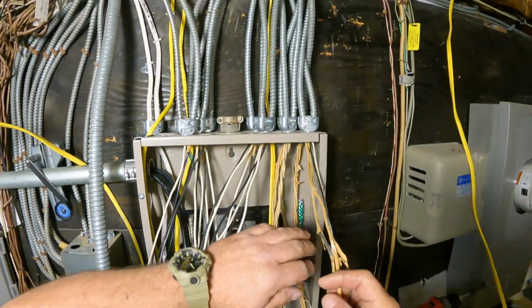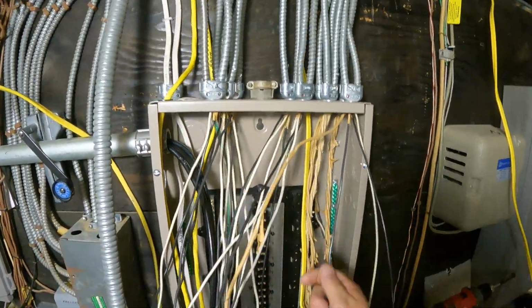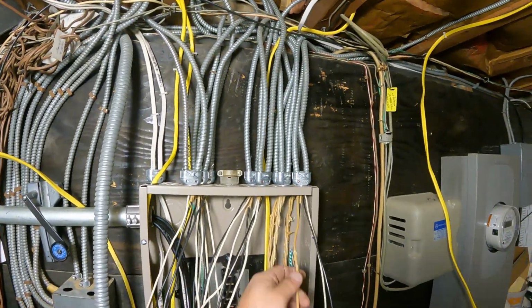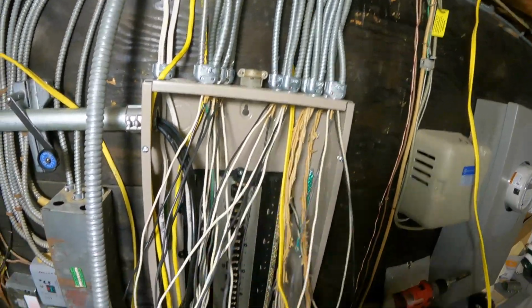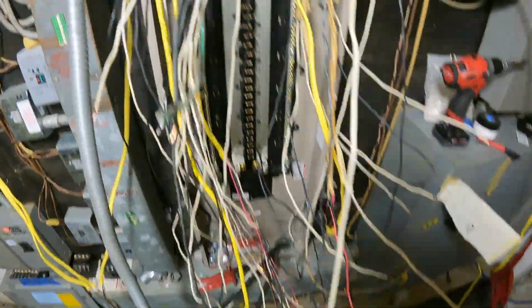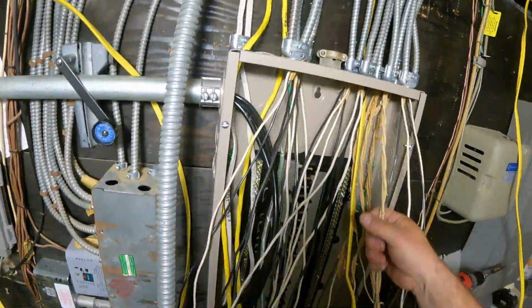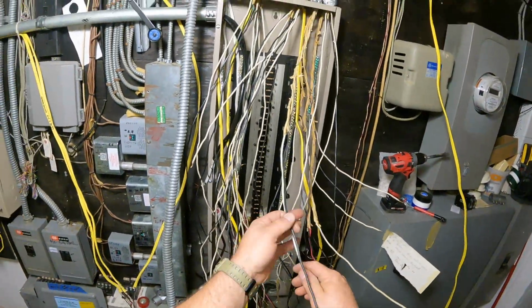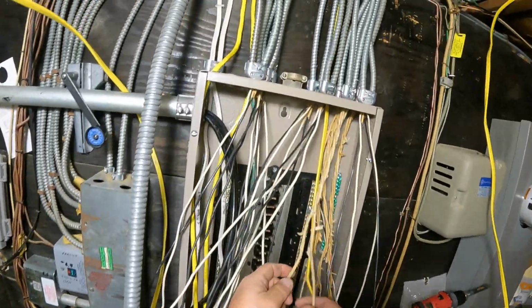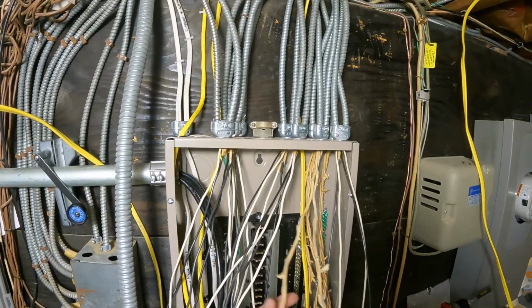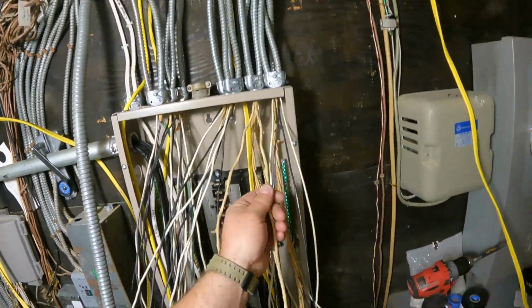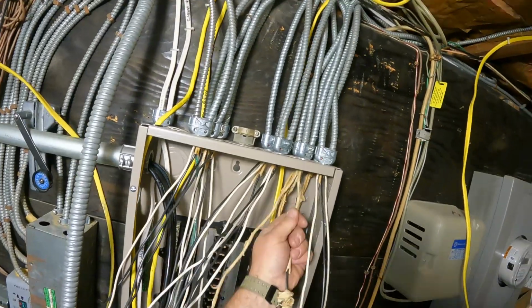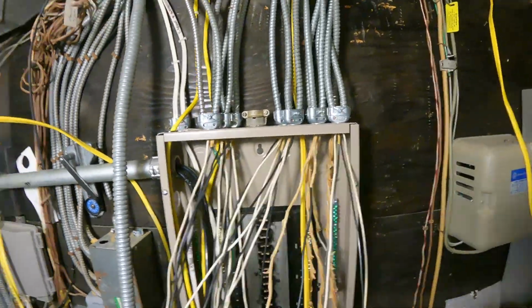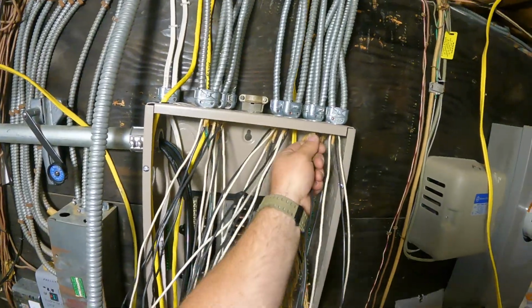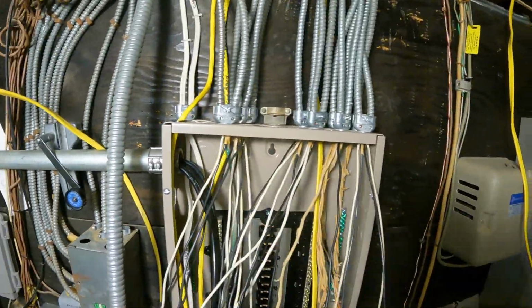Now that I have most of my branch circuits in this enclosure, I'm going to start peeling away the paper around these BX cables, which is standard, and then slice the sheathing off the Romex cables as well. Take your time with this, make these wires nice and neat. Right after this, we'll start separating our grounds, neutrals, and hots, and prepare to terminate these conductors. If you take your time, you'll have a nice, neat product when you're done.